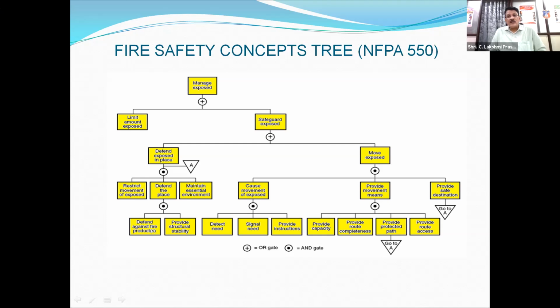Then moving the exposed: when we are moving the people, causing movement of the exposed, we have to provide a safe destination. Here again, in causing movement of the exposed, we need to detect the need, signal the need, and provide instruction. Here we use fire alarm systems, automatic especially, or manual if someone has seen it, because human beings are the best detectors of smoke or fire, since they can sense, filter, understand, and give the alarm.